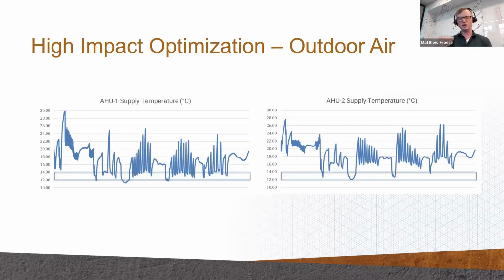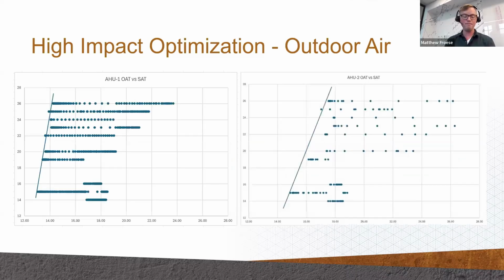So that data just lets you know something's off, but doesn't really tell you what until we add a third data point, which is the outdoor air temperature at the time. And this is a fun chart because this is a negative space chart. What's important here is the performance envelope. As the outdoor air gets warmer, as we're going up on the left axis there, air handler 1 is still able to push pretty cold air, but air handler 2 never manages to push cold supply air.